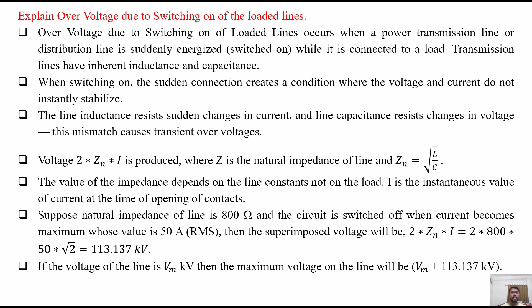Suppose natural impedance Zn is equal to 800 ohm of a transmission line, and the circuit is switched off when current becomes maximum, whose value is 50 ampere, suppose in RMS. Then the superimposed voltage will be 2 × Zn × I = 2 × 800 × 50, that is the RMS value, multiplied by root 2 for the maximum value. So it will give you 113.137 kilovolt. If the voltage of the line is Vm, that is the maximum value, 132 kV, 66 kV or anything Vm kV, then the maximum voltage on the line will be Vm plus 113.137 kilovolt. So this is how the overvoltage is produced due to switching on of the loaded lines.